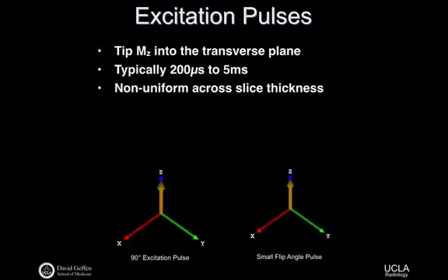Yes? How different are they? It can be very big, and it depends. If you have more of an EE background, it depends on the bandwidth of the RF pulse. If it's sufficient to excite all of the frequencies in the slice, then you can do better. But a high bandwidth pulse is going to be longer in duration. So there are these trade-offs in MR between really short RF pulses and really long RF pulses. And we usually make a compromise.